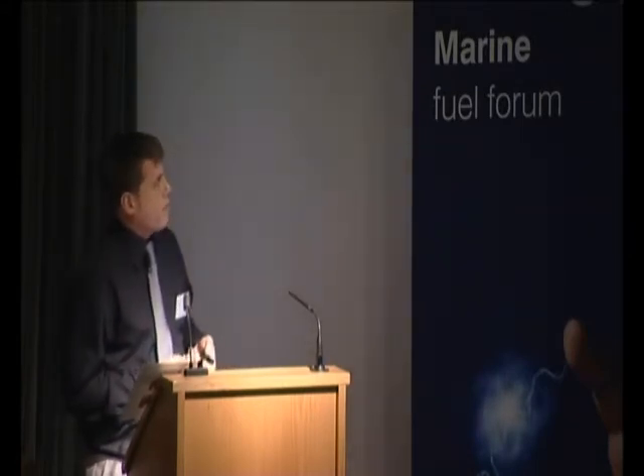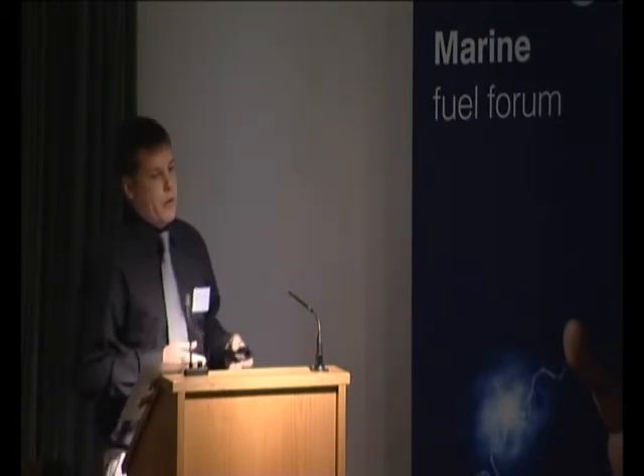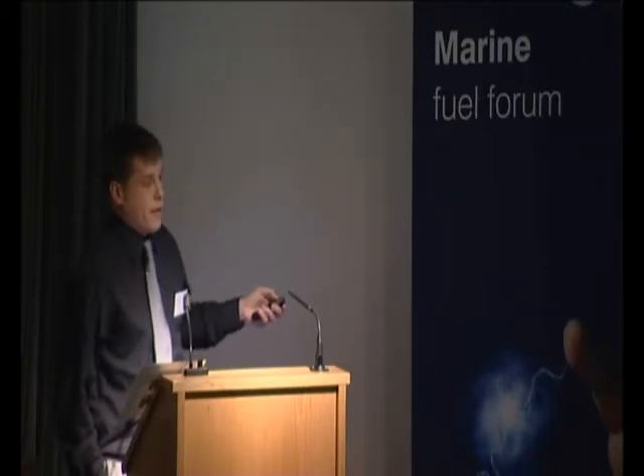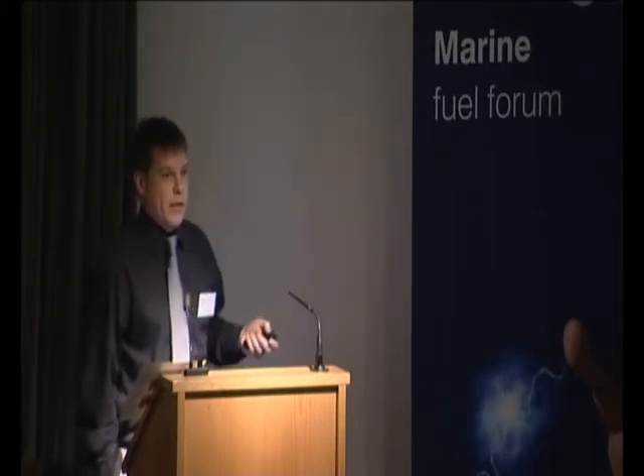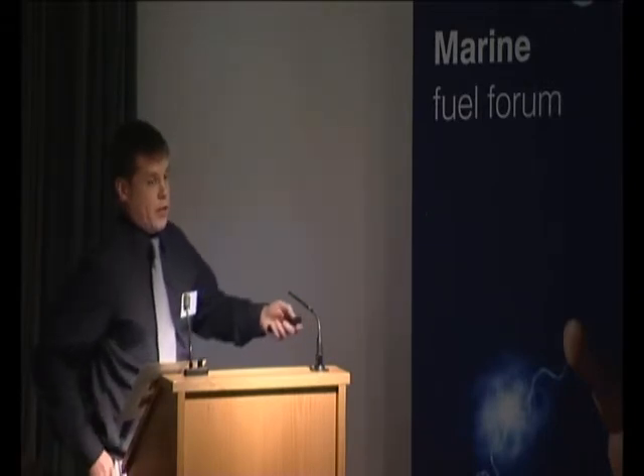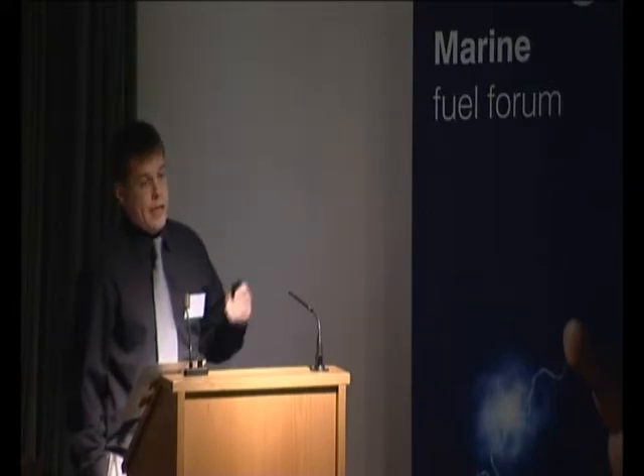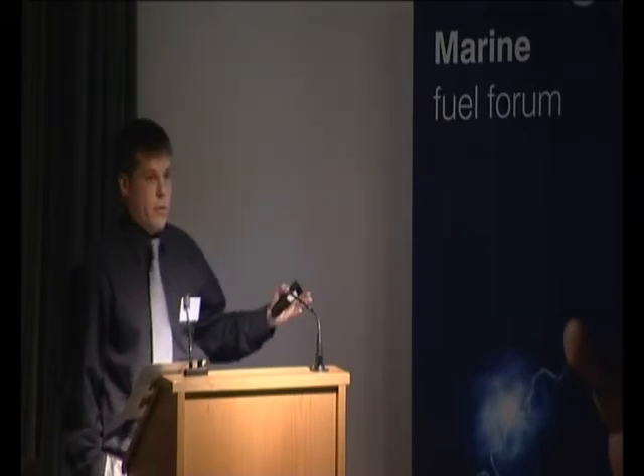This is another tank. I'll put this picture in here because it demonstrates the problem with the distance between the suction point and the delivery point. This is the end of the tank which is about six metres away from the fill point and the suction point. The fuel at this end of the tank does not turn over, so what you end up with is oxidised product and high water content, which is exactly what bugs like to live in. It's very important that you risk assess your tanks. If your tanks have a fill point and a suction point a long way from the end of the tank, you're quite likely to get a build-up at the end which will eventually come towards the suction point and cause a really big problem. Ideally, you want the system set up so you get as much turnover of product as possible — fill at one end and the suction point at the other.